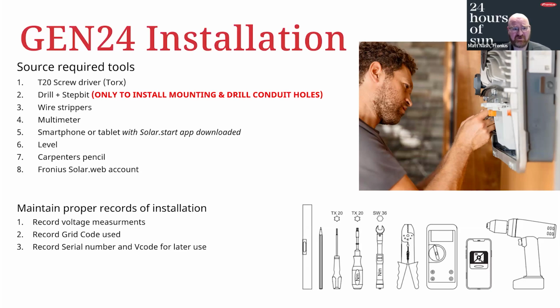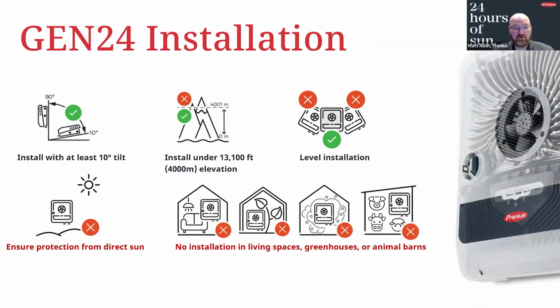If you are going to connect it to a SolarWeb account, then you'll want to sign in to the Solar.start app. Once you're finished, it will actually take you straight into SolarWeb to add it to a system. Some things that most installers should be doing is recording voltage measurements, recording the grid code that's being utilized, and the serial number and V code for later use, which can be found on the sticker on the right-hand side.